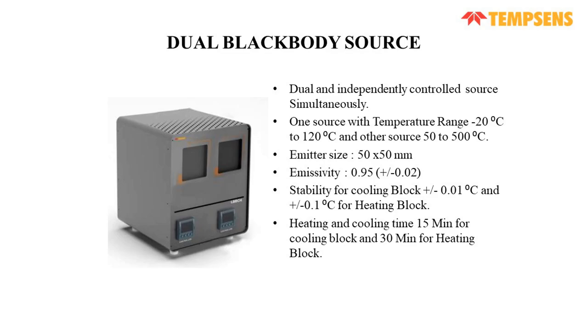Dual black body source. It is the same as the dual dry block we had in the earlier slides. In this one, the whole temperature range is minus 20 to 500, with one emitter from minus 20 to 120, and the other from 50 to 500. Emitter size is 50 by 50 on both sides, with emissivity of 0.95, and stability is plus minus 0.01 for the cooling block and plus minus 0.1 for the heating block. Heating and cooling time is 15 minutes for the cooling block and 30 minutes for the heating block.